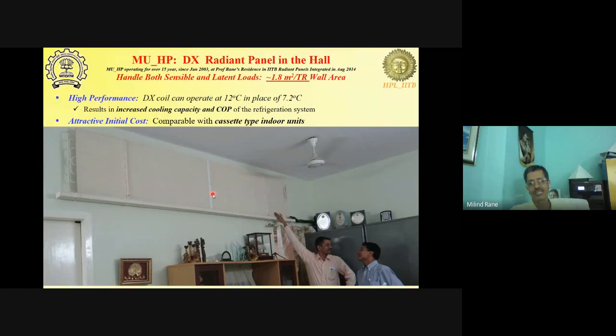Now, just to give you some idea about the benefits of this, not only does it give me a higher evaporating temperature, so the 1.5-ton compressor gives me almost 2 tons of cooling using the same compressor, and with a higher COP. The power input typically is around 1.4 kilowatt or even lower for a 2-ton capacity. So that's a very high efficiency, while it is also generating hot water. The best part is that this heat exchanger which I have deployed, I have not cleaned for the last 6+ years. Not a single time have I cleaned this unit.